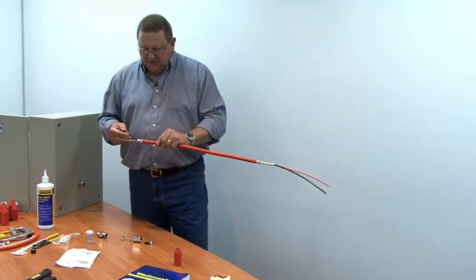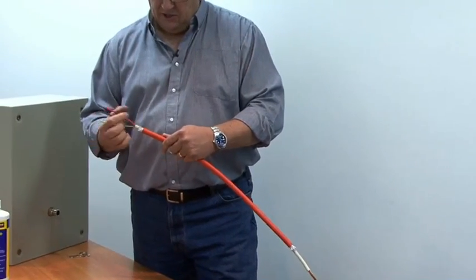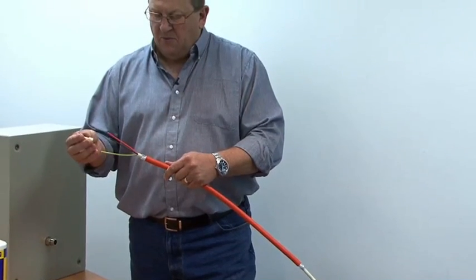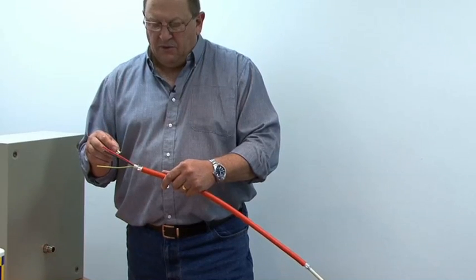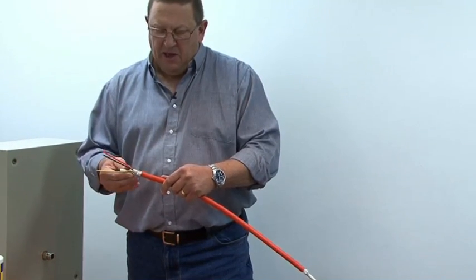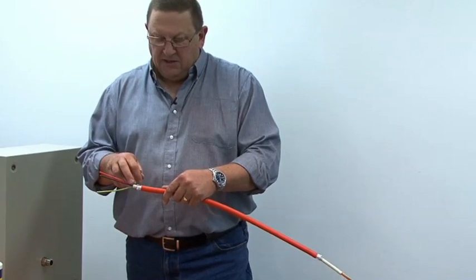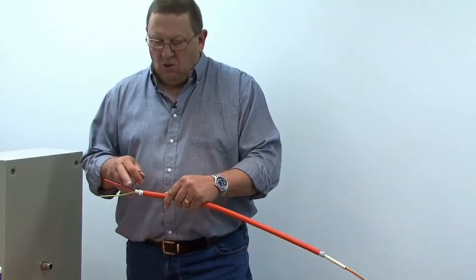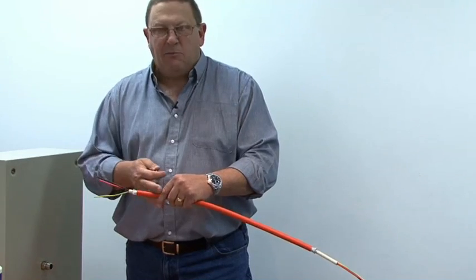In packing these conductors now, we'll mix up the putty, pack inside, fold the conductors closed, pack outside, and then when we insert this over the top, you'll find that the reduction in diameter by putting the cone over sees compression of all the putty around the conductors. We pack a little bit in the end of the cap and force it over the bedding, ensuring continuity of sealing with that two-pack epoxy all the way through, therefore excluding any path from the enclosure out through the cable build.